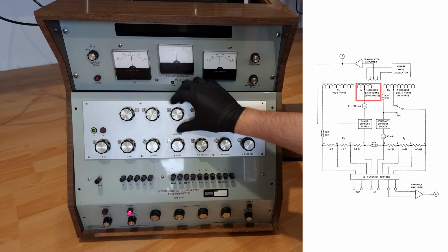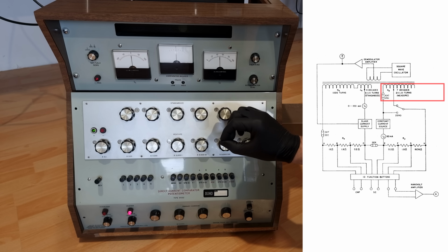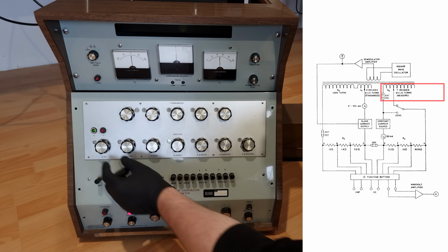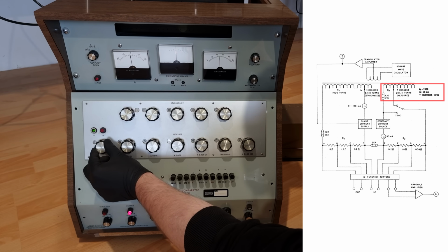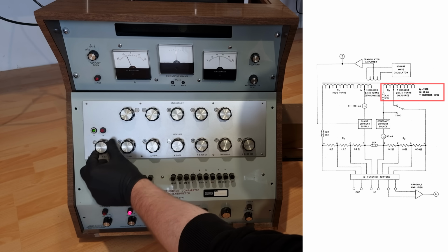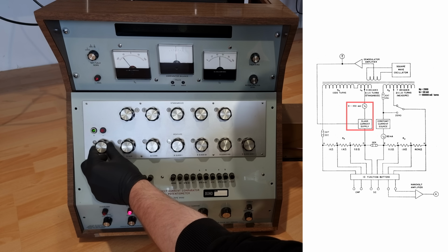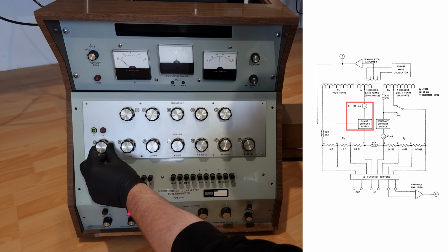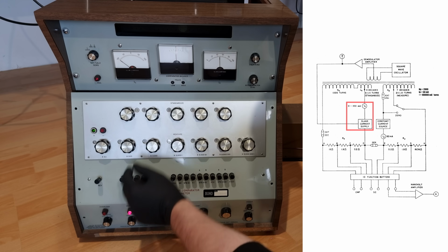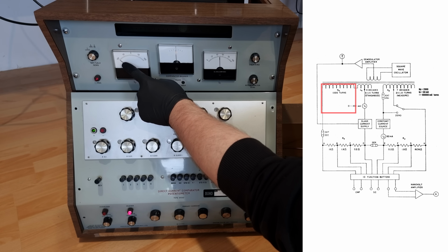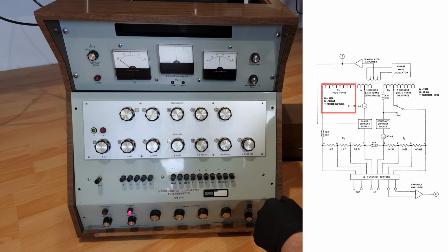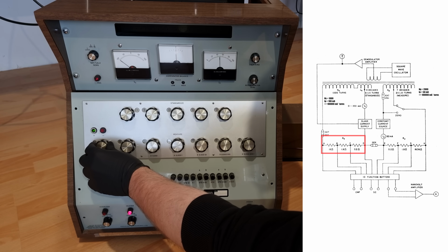have small offsets. Let's send our 50 mA primary current through 2000 windings. That would be 100,000 mA turns. To maintain comparator balance, the slave current supply has to send 100 mA through its fixed 1000 secondary windings. 100,000 mA turns again. And it does. Excellent. The secondary current also goes through a resistor, which the manuals call the forcing resistor.